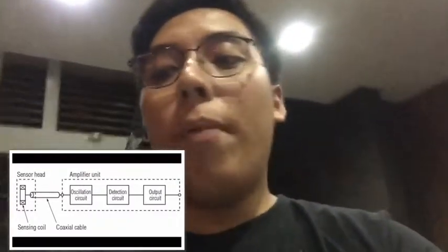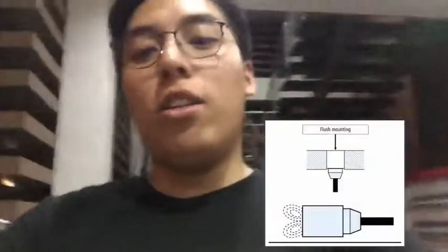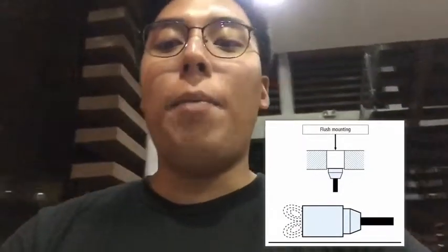It has a longer detecting distance compared with the self-contained type. The last one in the first classification is the amplifier in cable type. The sensor can be used as soon as the power is turned on. It has a small sensor head and amplifier. Sensitivity adjustment is not possible. In the second classification, we have the shielded type.